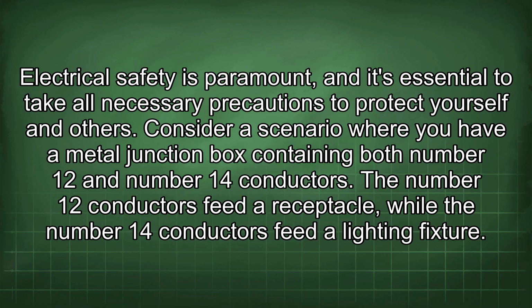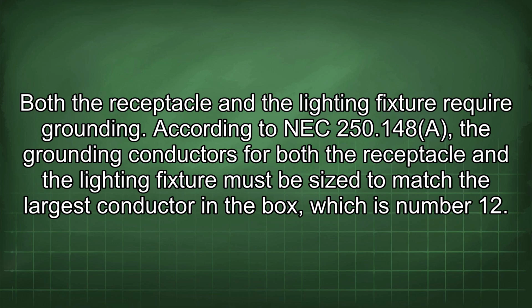Electrical safety is paramount, and it's essential to take all necessary precautions to protect yourself and others. Consider a scenario where you have a metal junction box containing both number 12 and number 14 conductors. The number 12 conductors feed a receptacle, while the number 14 conductors feed a lighting fixture. Both the receptacle and the lighting fixture require grounding.